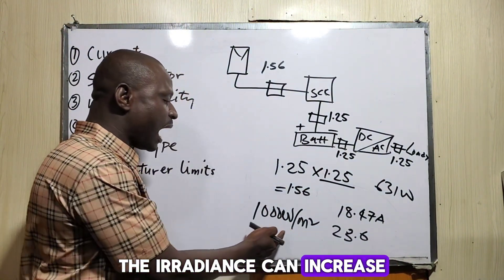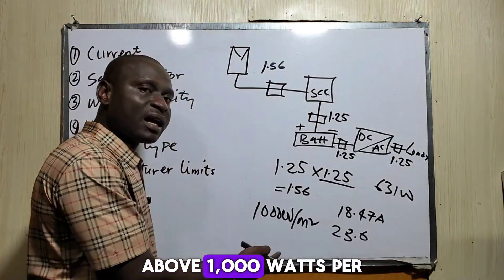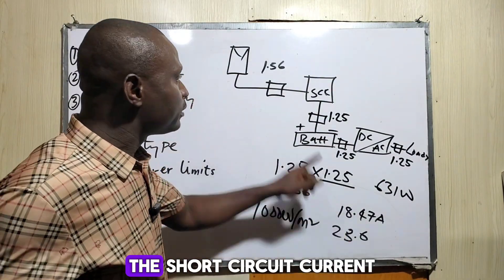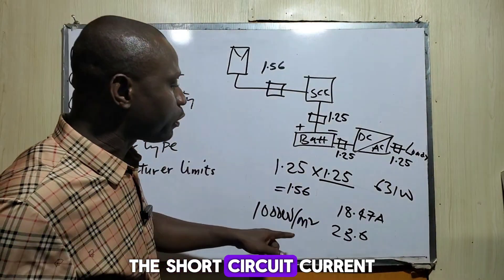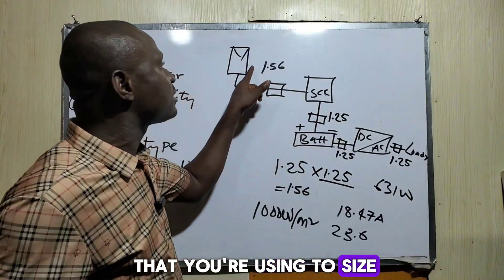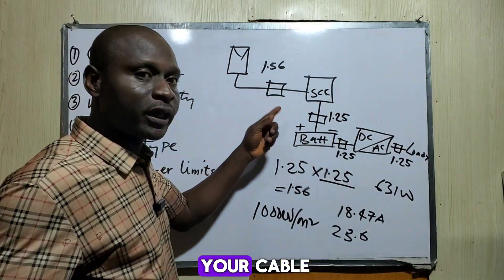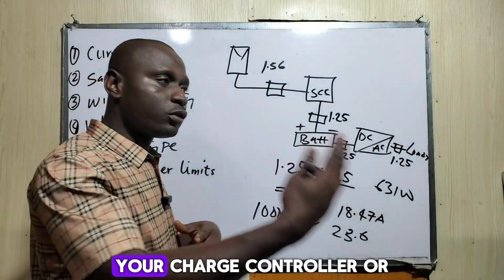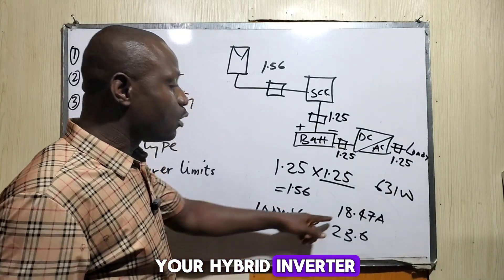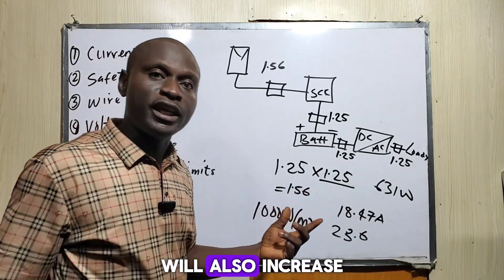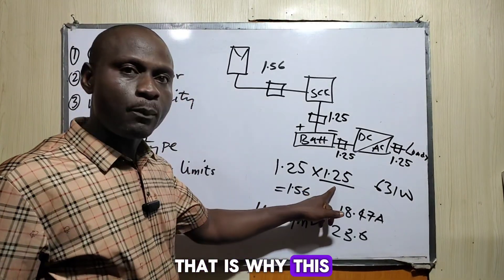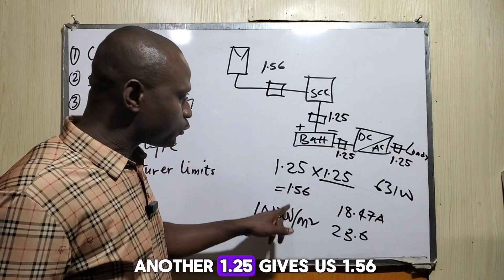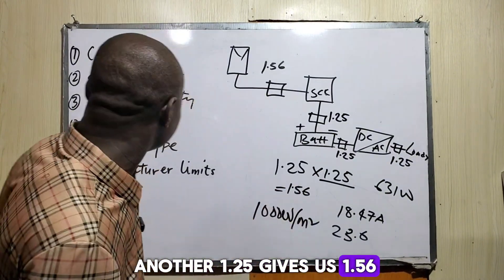The irradiance can increase above 1,000 watts per square meter, and when it does, the short-circuit current used to size breakers or cables between the solar panel and the charge controller or hybrid inverter will also increase. That is why 1.25 multiplied by another 1.25 gives us 1.56.